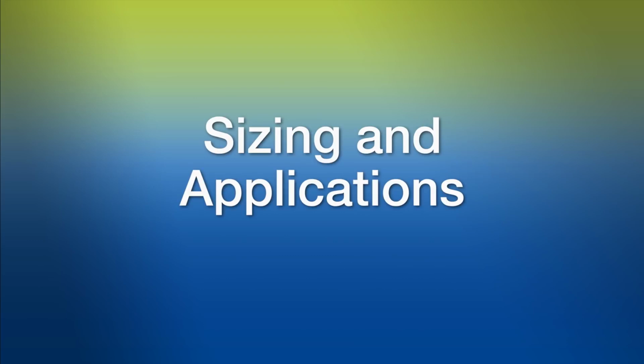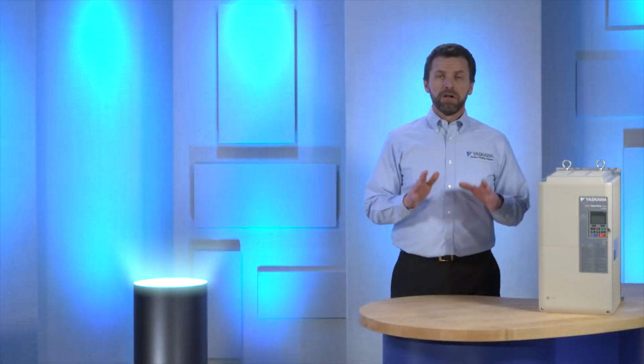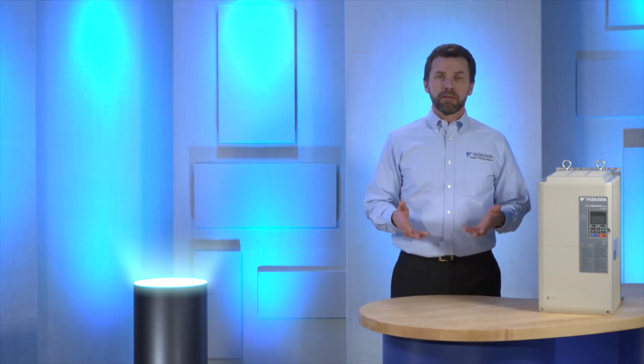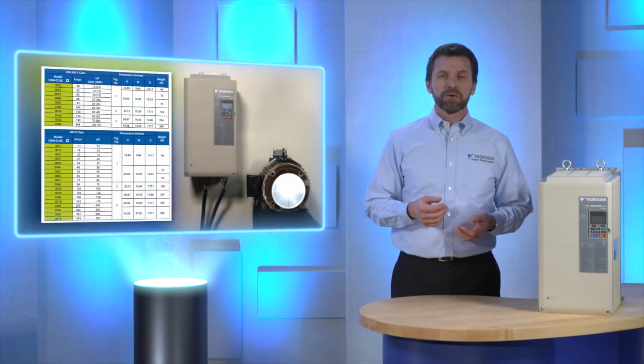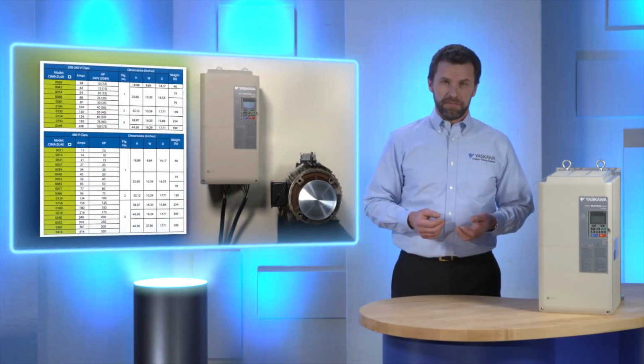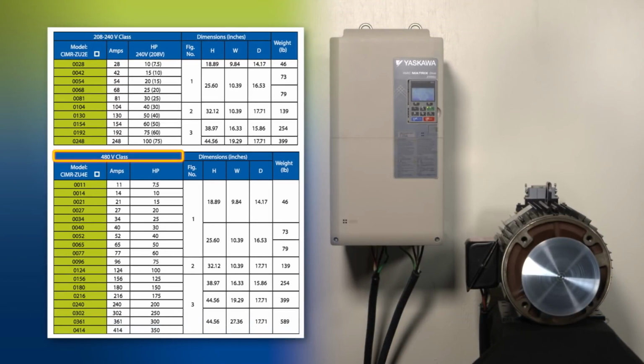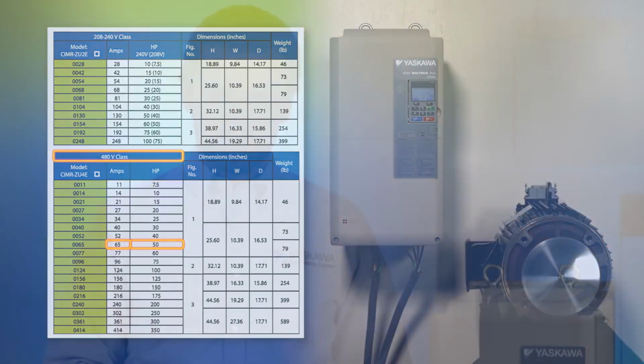Well, our next order of business is sizing and applications. Sizing the appropriate Z1000U is easy. It's just like sizing a standard drive. All Z1000Us feature output amp ratings that match NEC horsepower ratings. Simply match the voltage and current rating of the motor to the matrix drive. For example, at 480 volts, NEC rates 50 horsepower at 65 amps. And the 50 horsepower 480 volt Z1000U carries an output current rating of 65 amps.